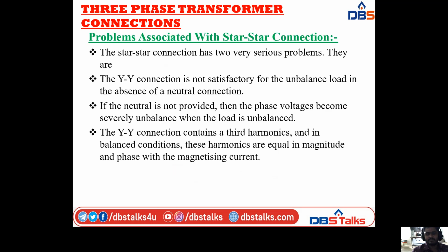Next, the problems associated with star to star connection. The star to star connection has two very serious problems. The first one is that the star to star connection is not satisfactory for the unbalanced load in the absence of a neutral connection. If the neutral is not provided, then the phase voltages become severely unbalanced when the load is unbalanced.